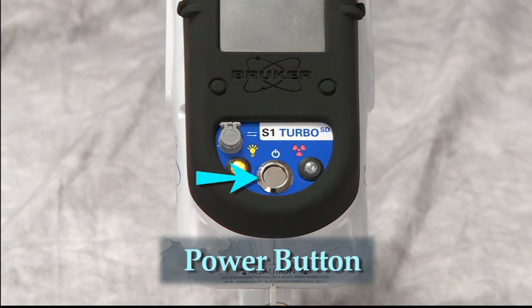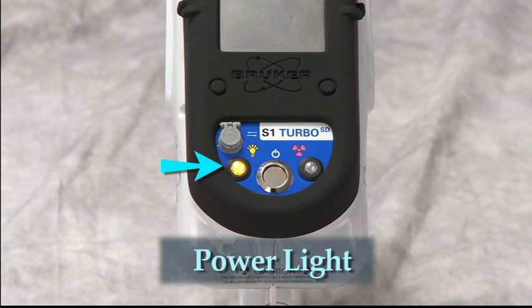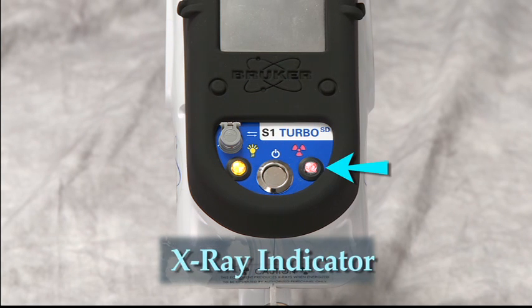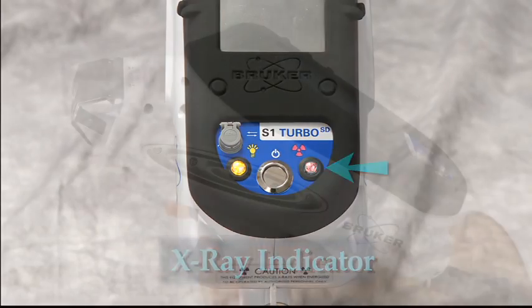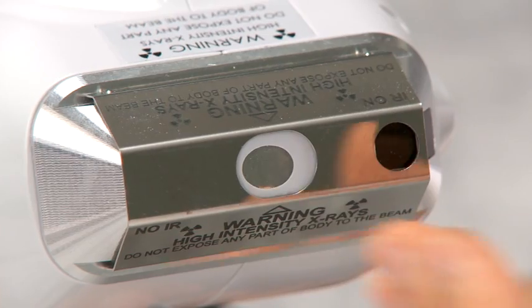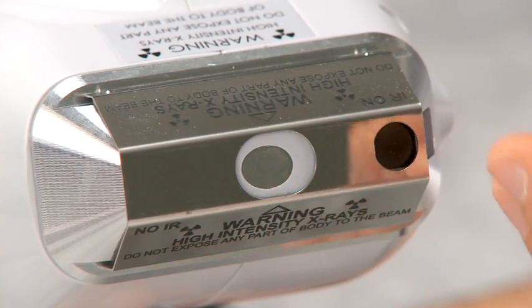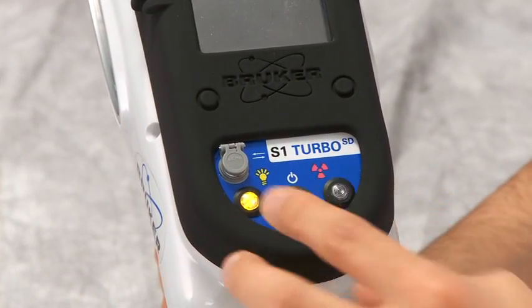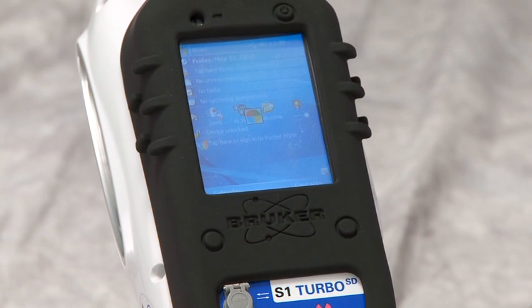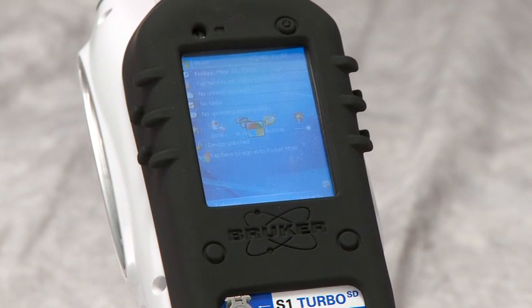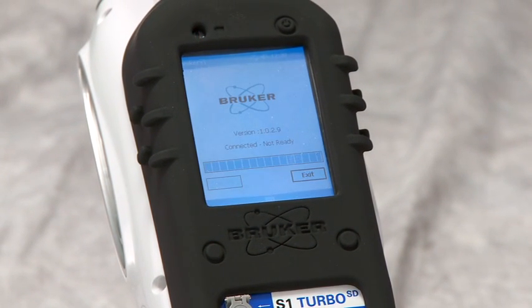The control panel of the analyzer has a power button in the middle, a yellow power light to the left, which indicates the analyzer is on, and a red light to the right, which indicates that X-rays are being generated. In the front of the analyzer are a measurement window and IR sample sensor. To start the analyzer, simply push the power switch on the control panel, and then the left button on the PDA cover, which is a shortcut to the calendar button on the PDA. This will start the login procedure of the analyzer.